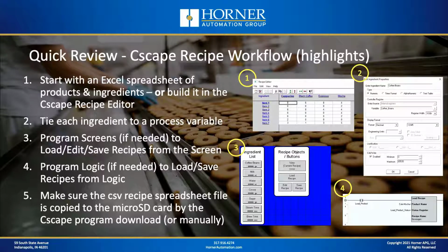So you're going to start with either an Excel spreadsheet that you create that includes products and ingredients along with their values, or for a lot of you, you'll just go ahead and start in the Cscape recipe editor, where by setting that up, you can effectively create that spreadsheet from scratch. Once you're in the Cscape recipe editor, either after importing your own spreadsheet or building one from scratch using that tool, you're going to tie each ingredient to a process variable.